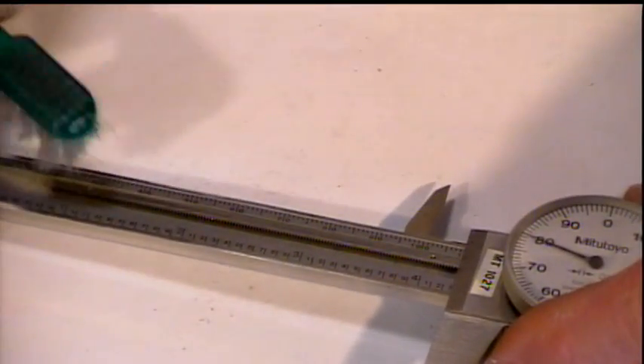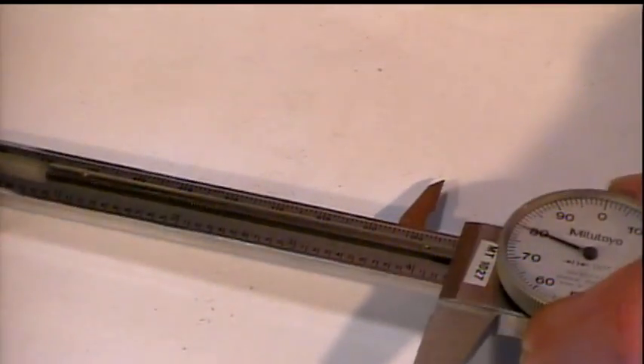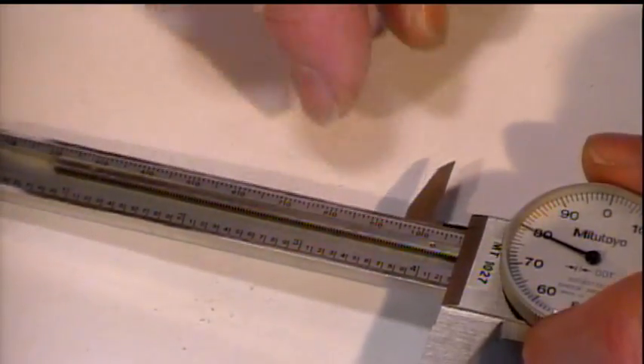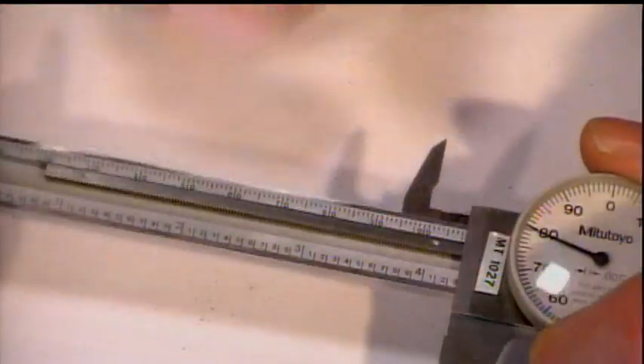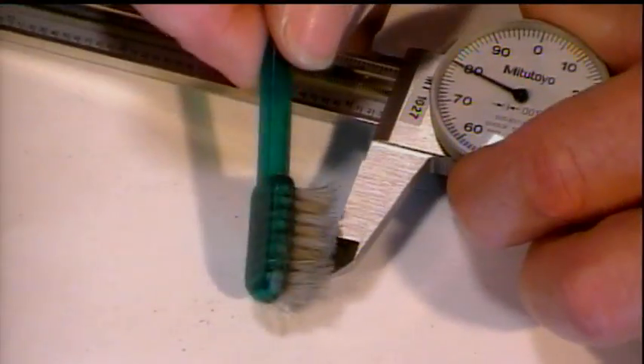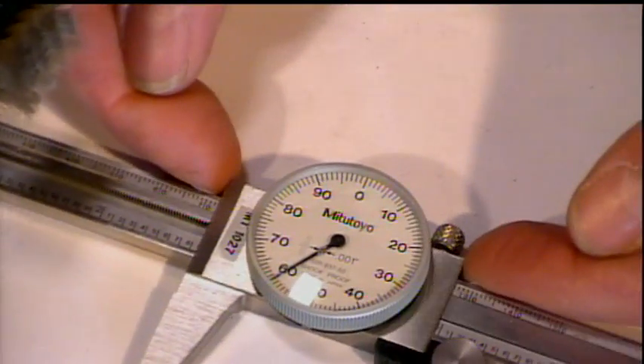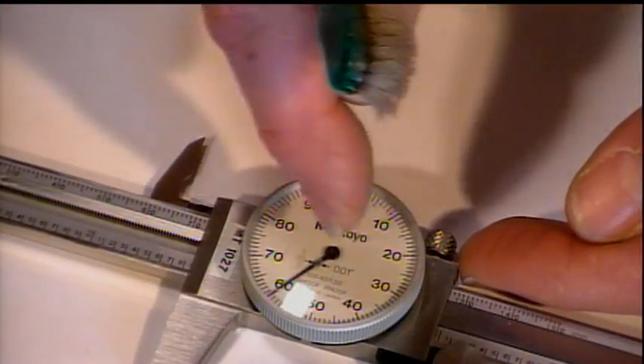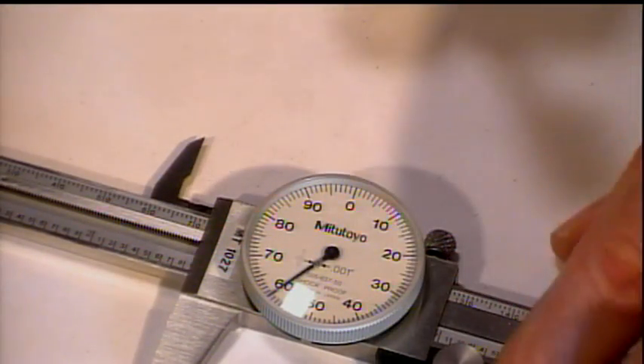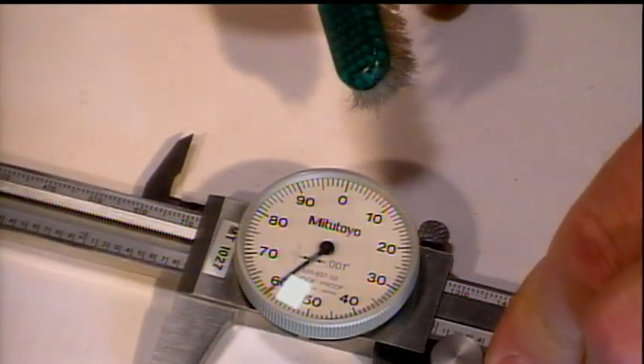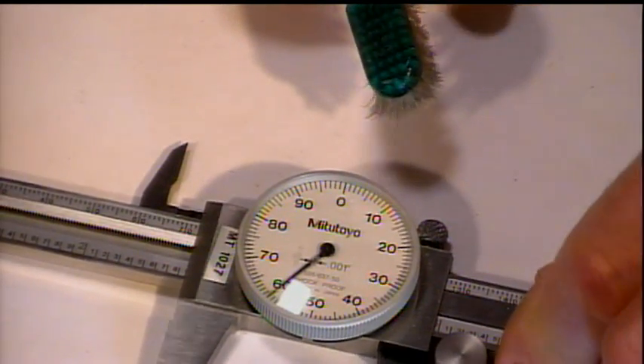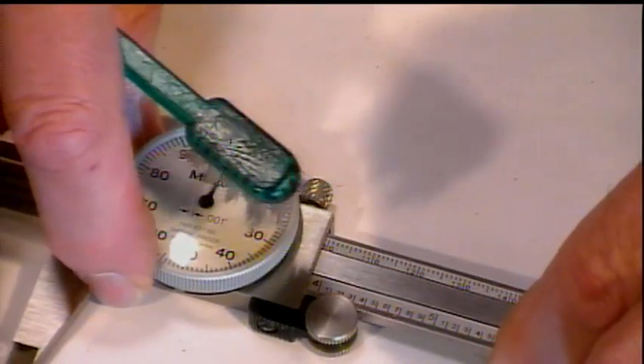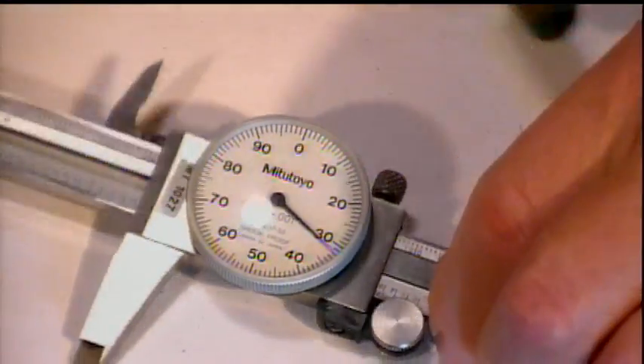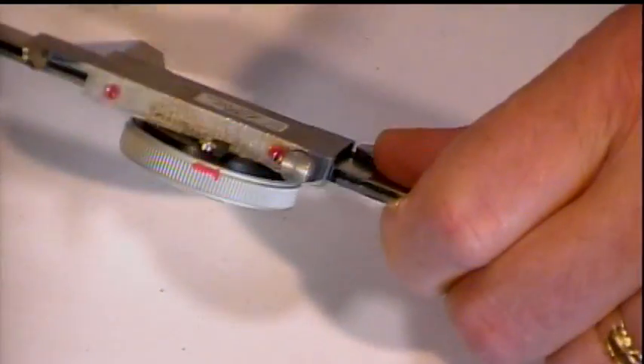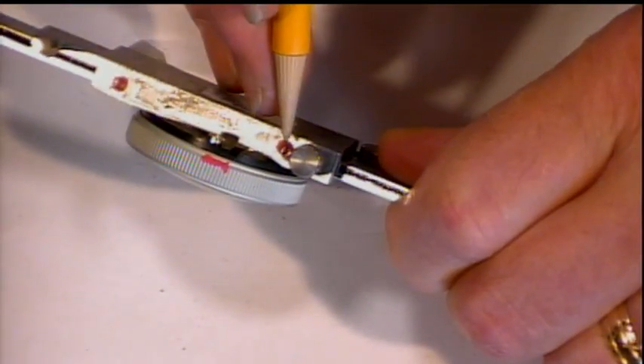So the first thing we will do always is clean these with the toothbrush. We'll just clean out the racks. Now, just a dry toothbrush? Yeah. You do not want to squirt alcohol in here. We will squirt alcohol on a rag and work the surface. But typically dry. We'll also use the toothbrush on the ends. And then up in this area here, inside there's a little, some might call it a leaf spring. It's called a gib. And it's usually a brass piece, some use nylon. And it's curved. It keeps tension on this. So when it slides along the rails, there's a little bit of tension. And there are adjustment screws on that gib. We don't suggest using them unless there's a problem.